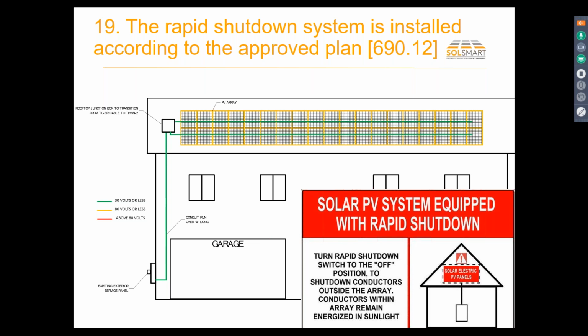So the conductors leaving the array are clearly down below 30 volts, which is the basic requirement of the 2014 code. The 2017 code after January 1 is going to require this lower hazard array. This particular sign is for the 2014 code, essentially. It's in the 2017 code, but it would comply with the requirements right now in the 2017 code and the 2014 code, which is conductors leaving the array are shut down, but the conductors within the array would remain energized in sunlight.